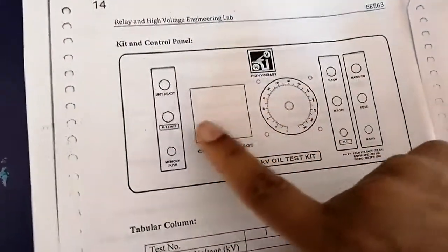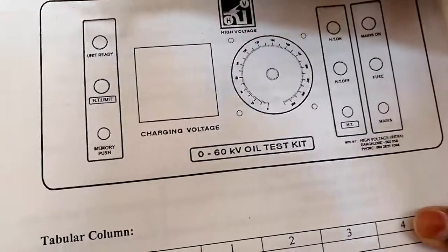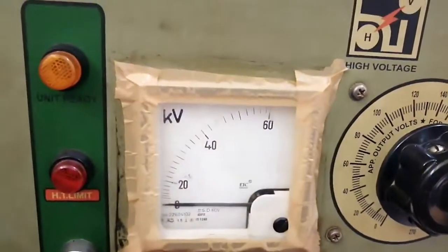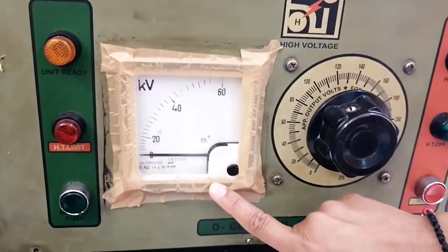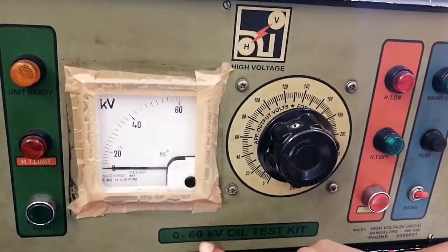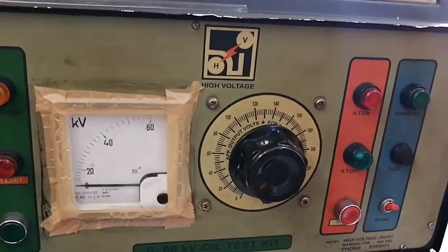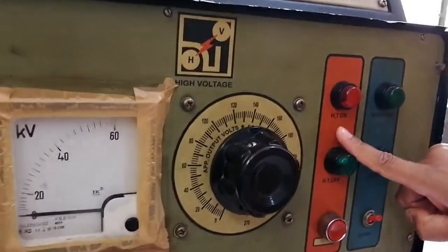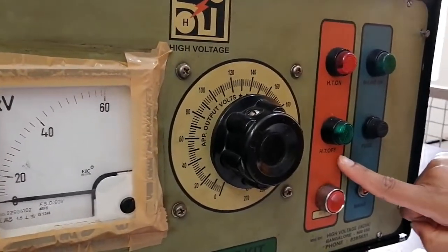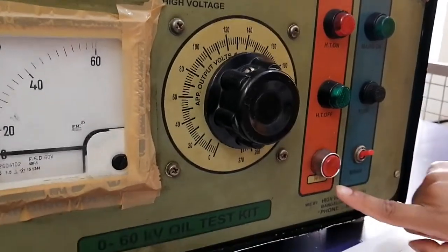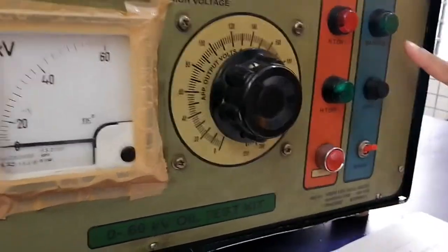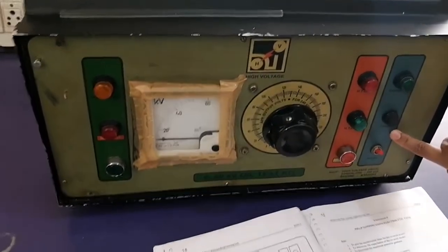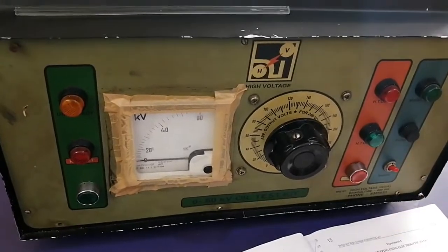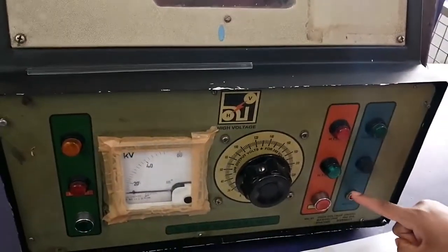So you can see here: unit ready, then HT limit, and this is the memory push button, then the voltmeter, then the transformer, the 0 to 60 kilovolt oil test kit, then HT on. This light will indicate whether the HT, high tension, transformer is ready or not. Next is HT off. Then this is the push button for turning HT on, and this is mains on. When you turn on the 230 volts, this light should turn on. Next, this is the fuse; if anything goes wrong, it will turn off. Then this is the main switch. Once you switch on the mains 230, you have to make sure this switch is also on.